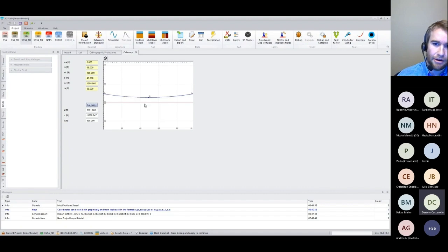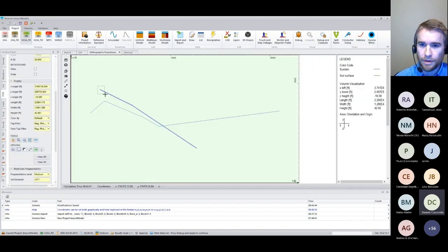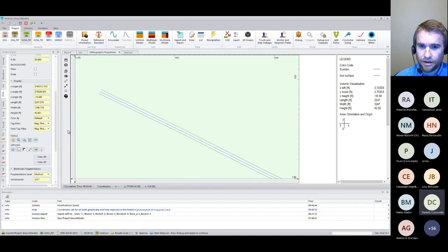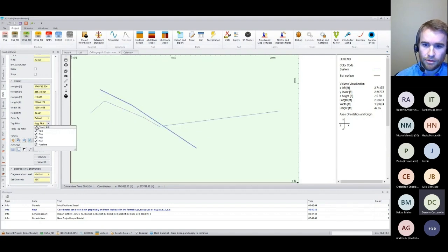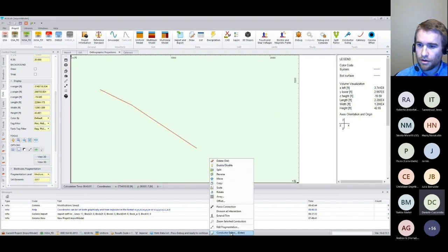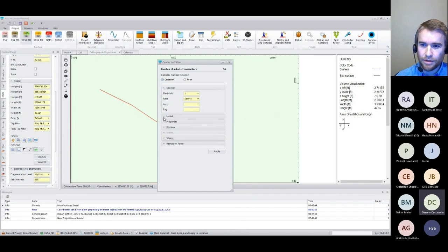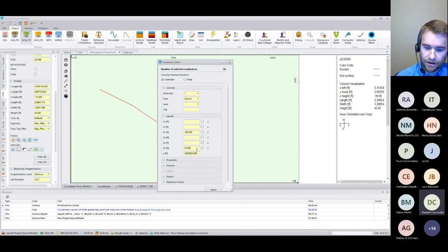So here we get the catenary curve characteristic, and I'll go ahead and select this A parameter. Going to my draw view, we'll zoom in again at these, and all of my phase conductors are right at the Earth's surface, which isn't ideal, and they don't consider that catenary curve. So I will select just phase A, B, and C, go to my conductor editors, and all of these are going to be edited in mass. So I want to elevate these to be negative 85 feet into the air and put in a catenary curve.